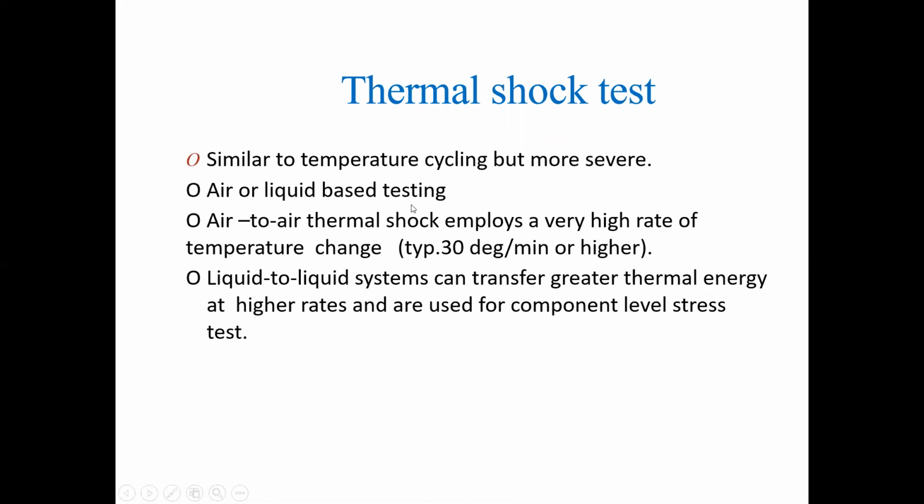Air or liquid based testing: air to air thermal shock employs a very high rate of temperature change, typically 30 degrees per minute or higher, and the liquid to liquid systems can transfer greater thermal energy at higher rates and are used for component level stress tests.